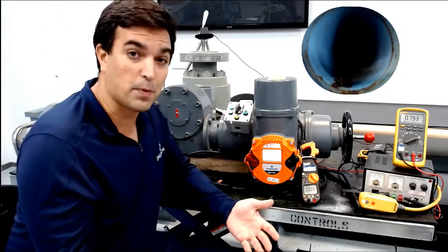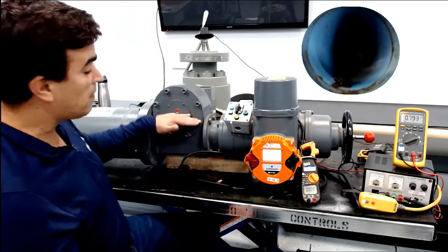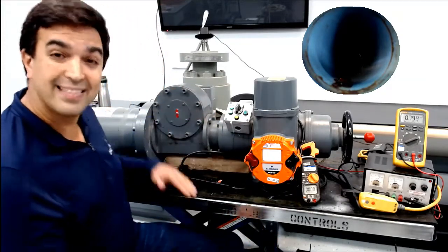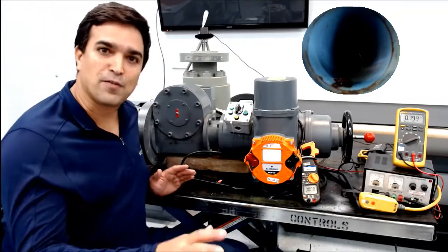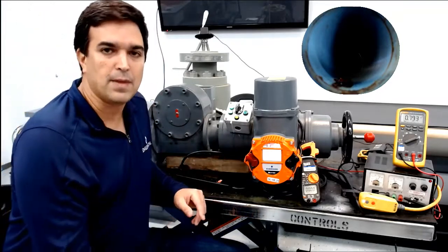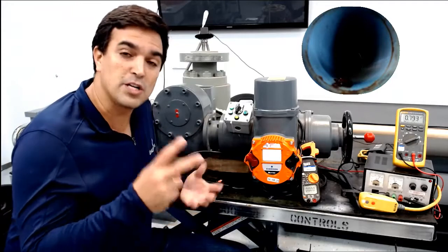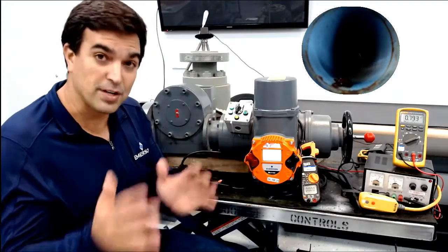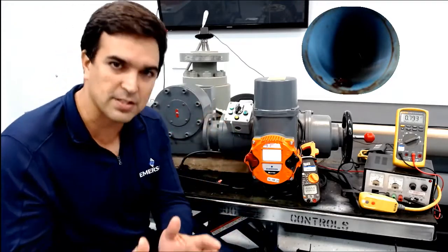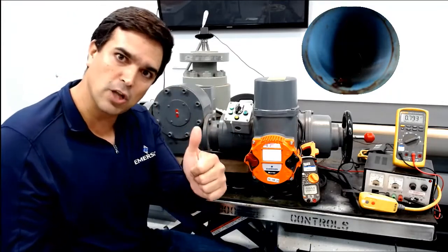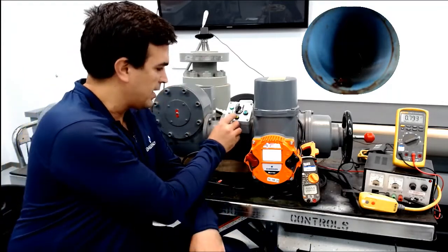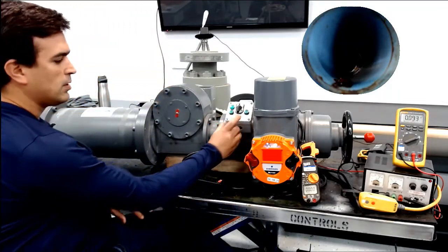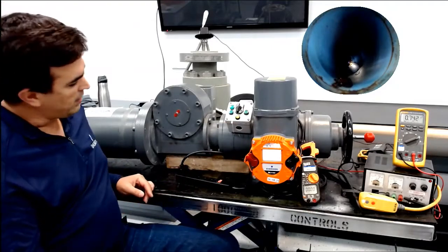It is going to trigger a second partial stroke, which is going to run the motor to 70%, and then bring it back after 5 seconds. If both situations happen in less than 30 seconds, 30 seconds the first one, 30 seconds the second one, it is going to give you a thumbs up and it's going to be okay. So trigger the partial stroke, there you go, it triggered.